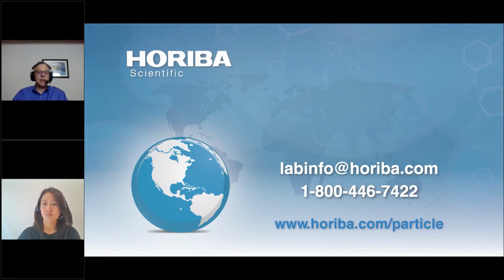Perfect. Thank you. Now, what kind of standard and dispersant are used for the HORIBA laser diffraction tool? Standards, we use two kinds of standards in our laser diffraction tools. And we actually have a talk on, I think the title was validation. But we use narrow polystyrene latex standards. The nice thing about them is they're inexpensive, they're quick to use, and they're a good test of your optical system. So you put in 1 micron polystyrene latex, you get 1 micron out, boom, everything's good. Your optics work fine.